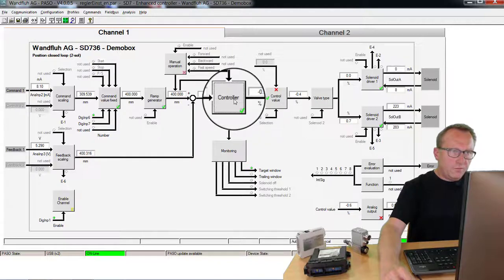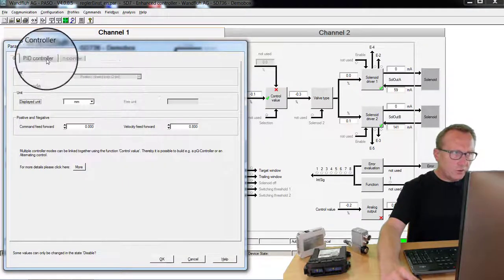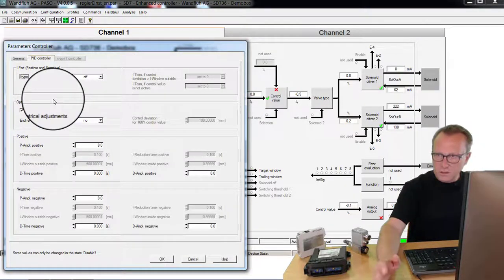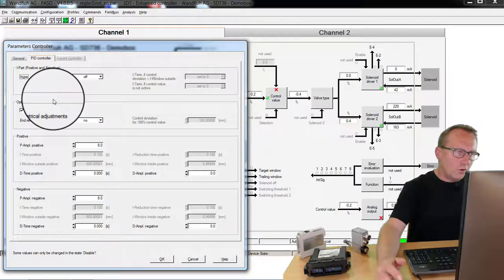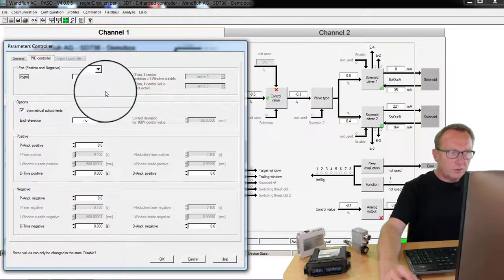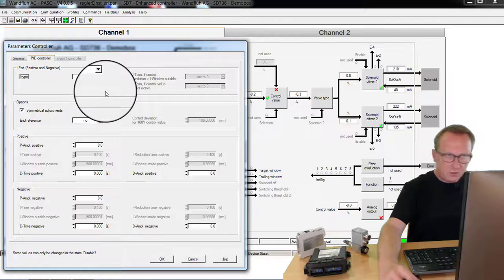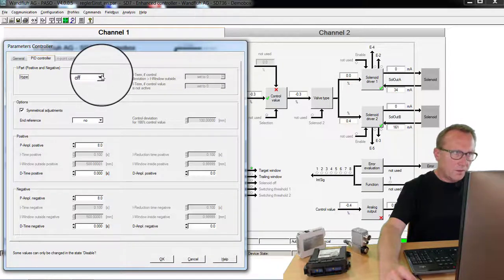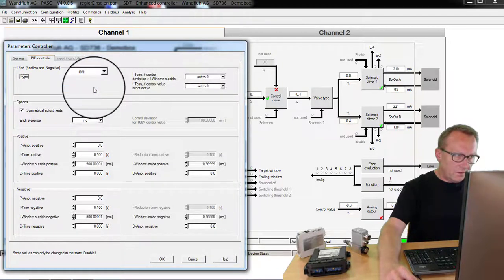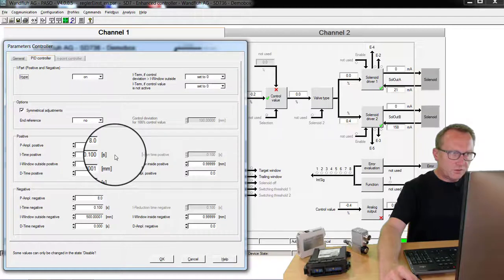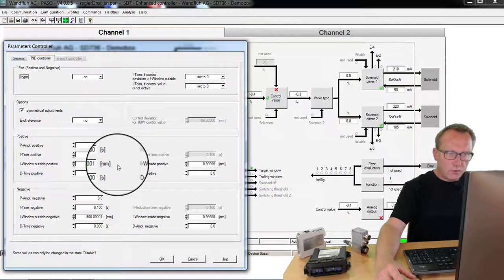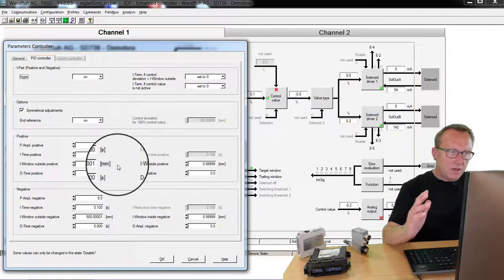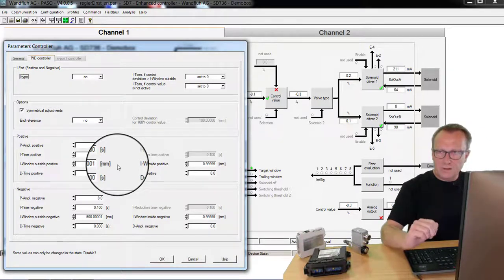If you are working in a position control, then the P part is enough. If you have a flow or pressure control, you should also use the integration part. You can switch it on here. Then you can adjust the time. And you can adjust a window in which the I part should be active.